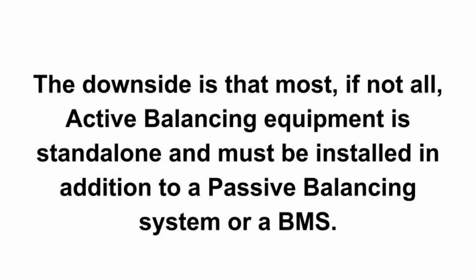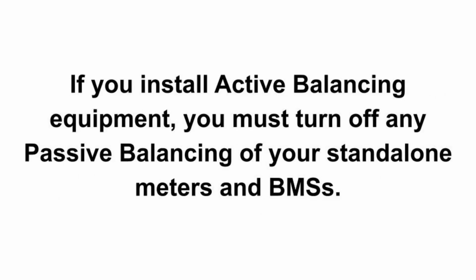The downside is that most, if not all, active balancing equipment is standalone and must be installed in addition to a passive balancing system or a BMS. If you install active balancing equipment, you must turn off any passive balancing of your standalone meters and BMSs.